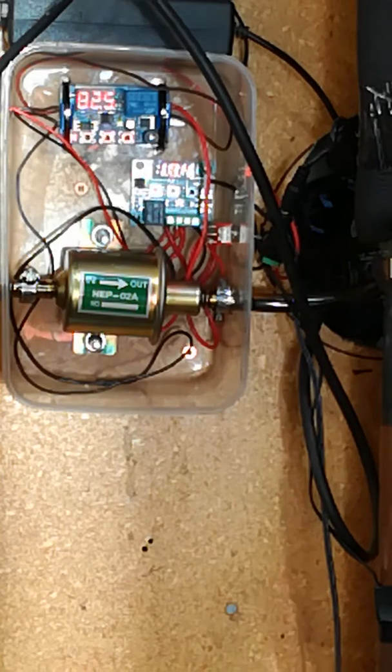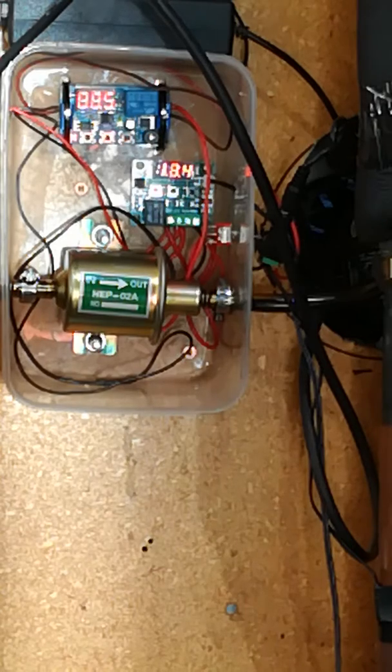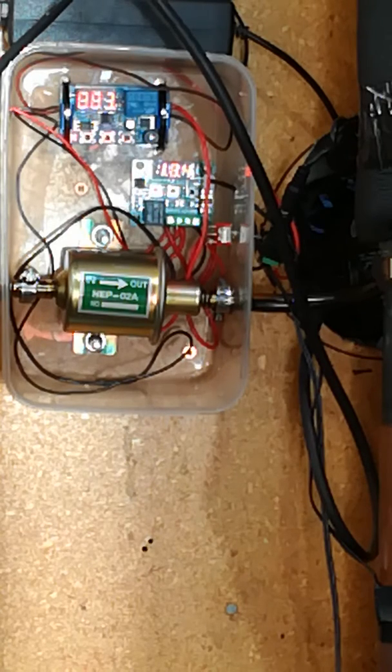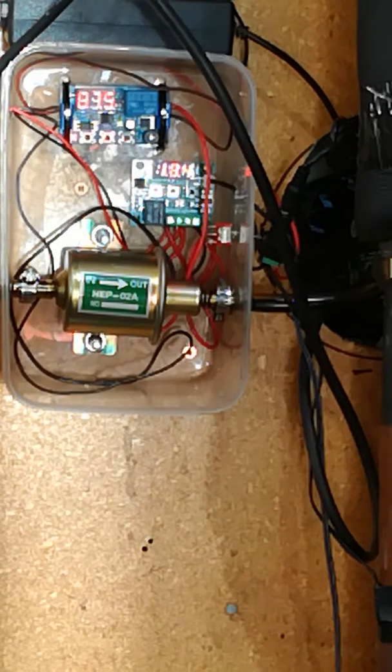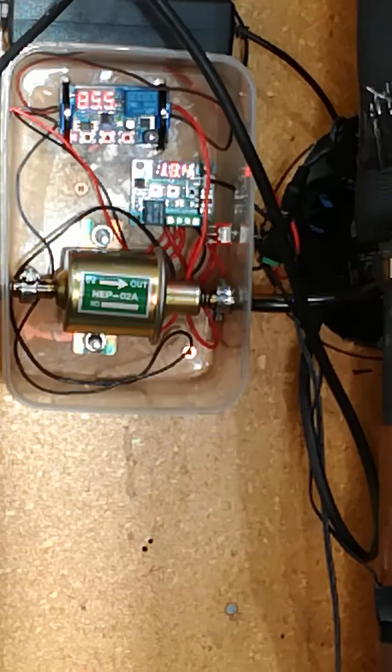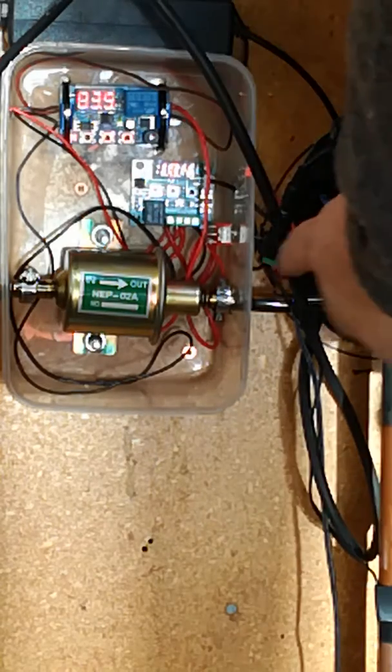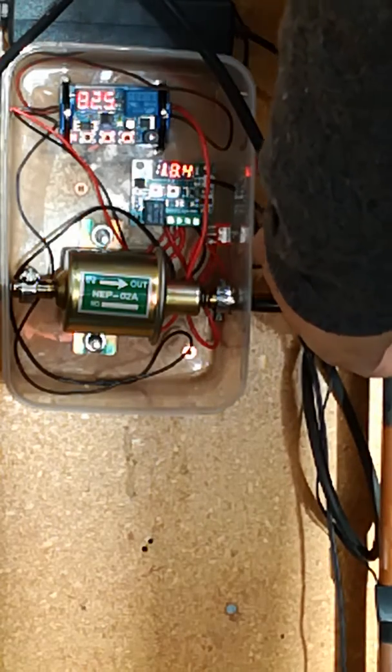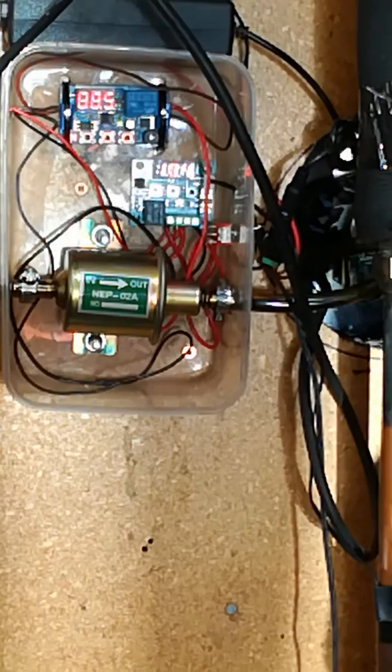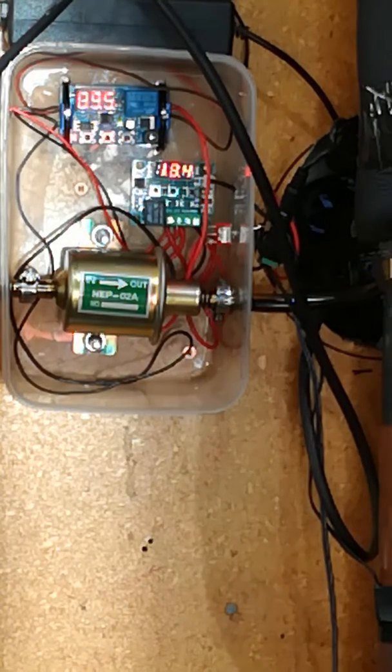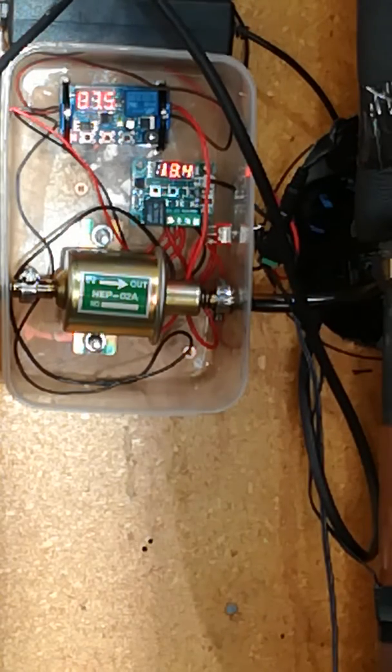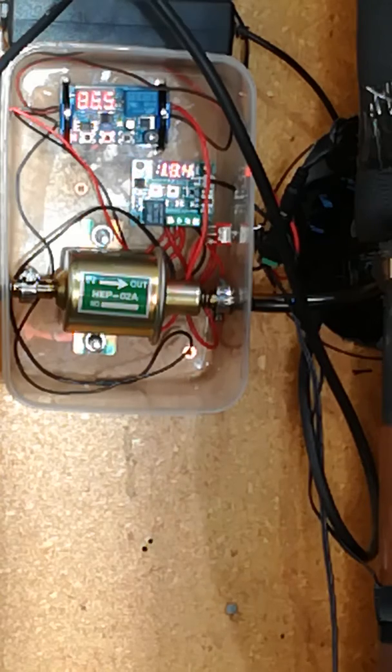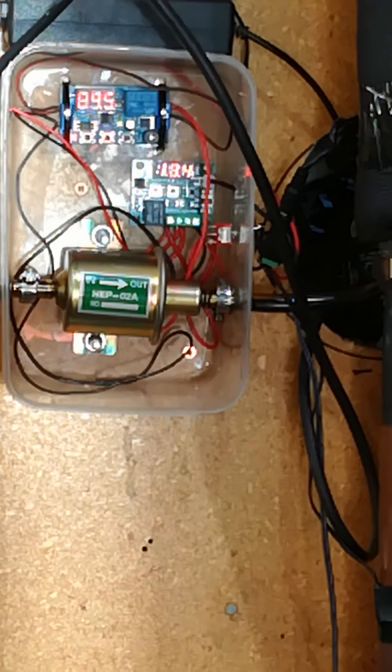We have a bypass on the thermostat because it's hard to light with the thermostat connected, so we have a little bypass switch on the side. What that does is bypass the thermostat and turn it on after you've lit it and you've got a bit of heat in the pump.